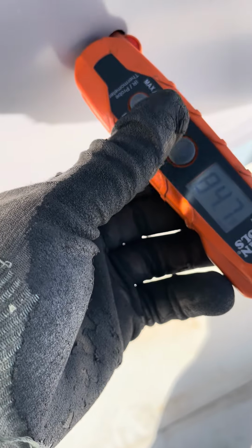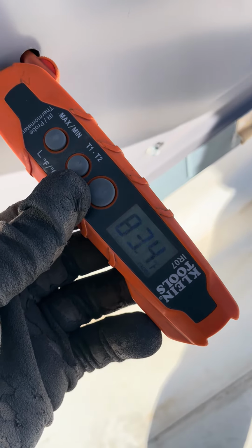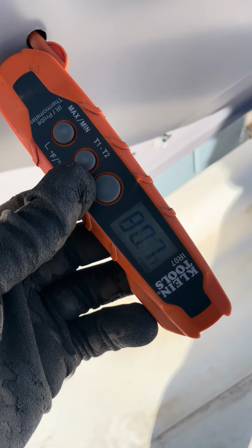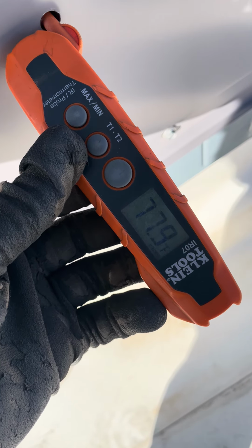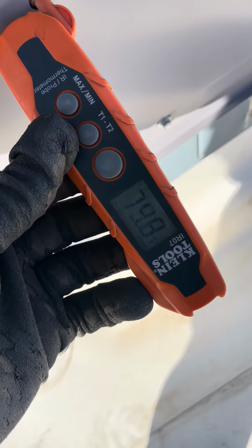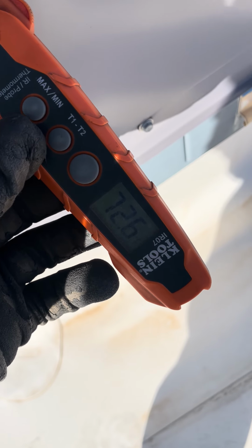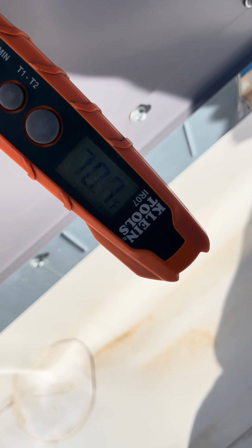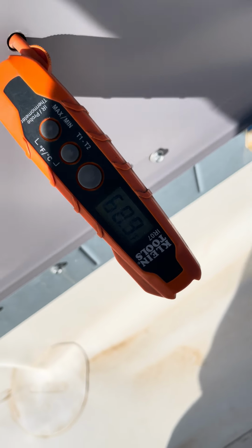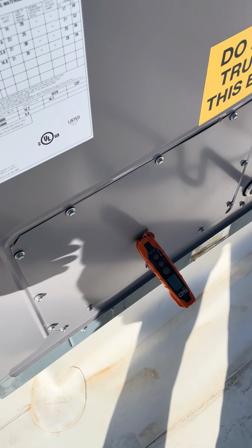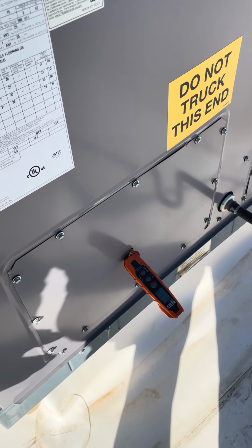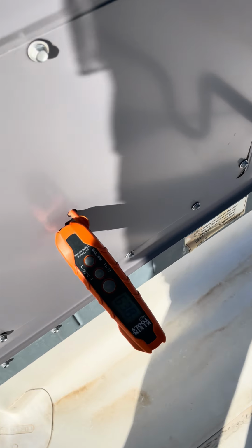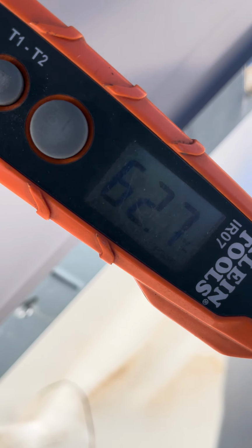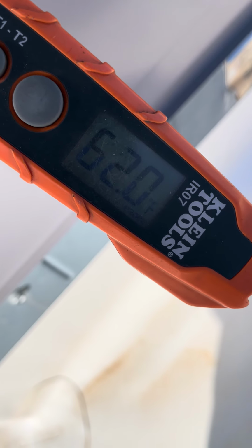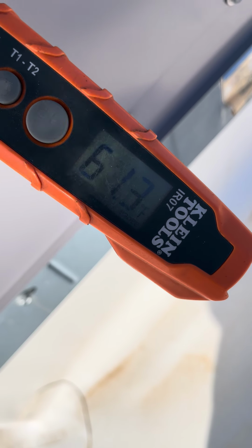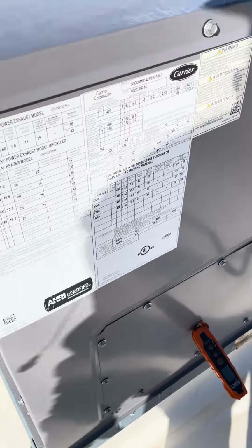So turn on the temperature probe. Temperature dropping. So that relay just has bad contact. The bottom contacts were not good. I switched it to the top contacts, and we still have cooling right now. So the unit will operate in heating and cooling as normal if the EMS is calling for heating or cooling inside of the building. But we don't want the unit to just be heating, especially when they're calling for cooling. The temperature is dropping down where it's supposed to go, so that's a plus. That's all I have to show you for today.